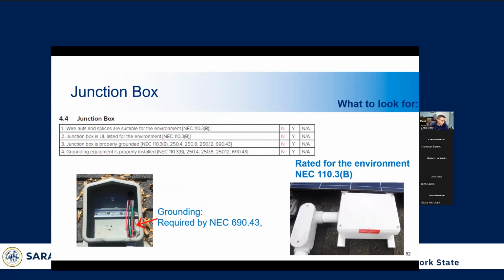All right, so now we'll look at junction boxes. If an enclosure is mounted on the roof deck, it has to be properly flashed and sealed, as you can see on the left. This is properly flashed and sealed. However, a conductive enclosure, this is a metal enclosure, so it's conductive. If you have electrical wires coming through here, it's considered likely to become energized, and it's also supposed to be bonded and grounded throughout the ground path. You can see a ground lug here, and they have the ground wire running through, and it's never terminated in this enclosure, so that would fail.